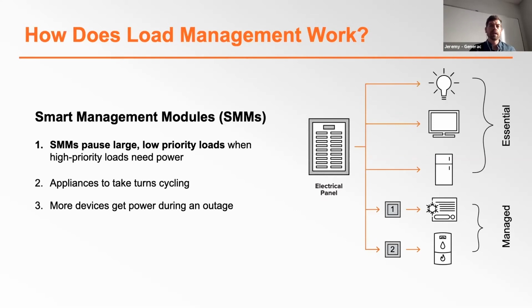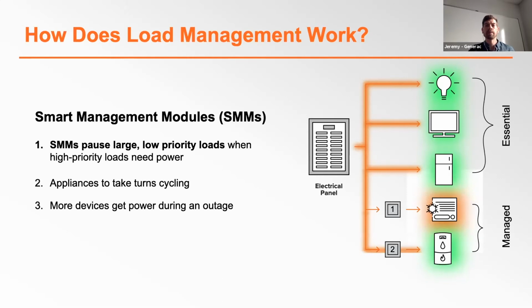So you can see that the air conditioner and the hot water heater are being managed by SMMs. The hot water heater is priority number 2. And in this example, the hot water heater, we're going to see, is currently drawing power. And then the air conditioner is going to try and start. This stresses out the system, okay? The system recognizes that trying to run both of these big loads at once is going to overwhelm it.